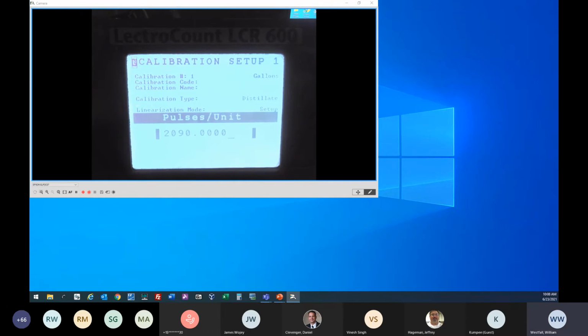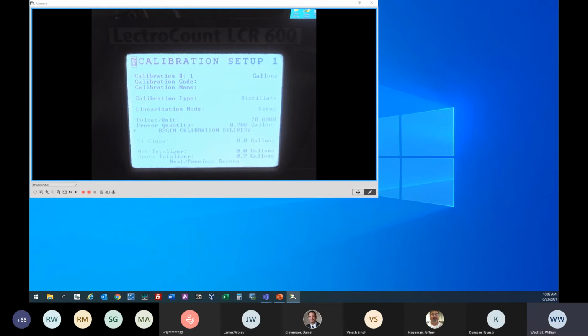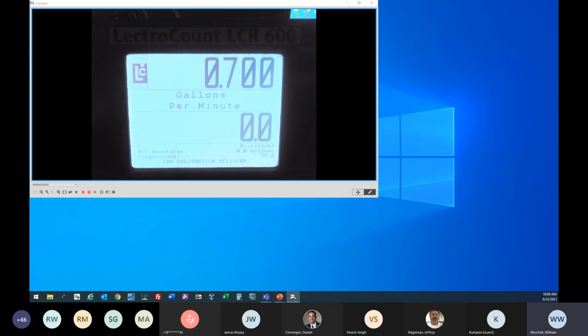So again, let's do this again. Let's start back at 20, so we can get a better proving run. So we go down to begin calibration delivery. Go ahead and hit the enter key. We get a counter test. And now we actually make a delivery.